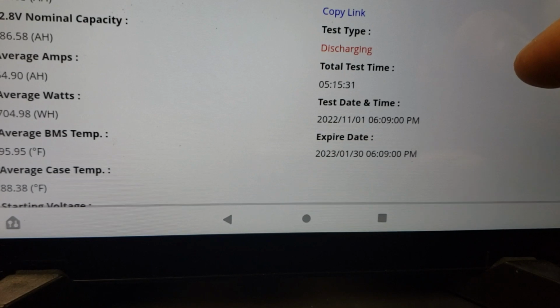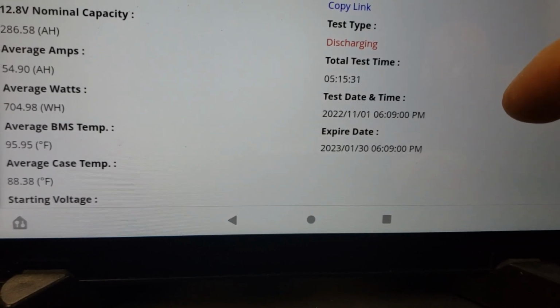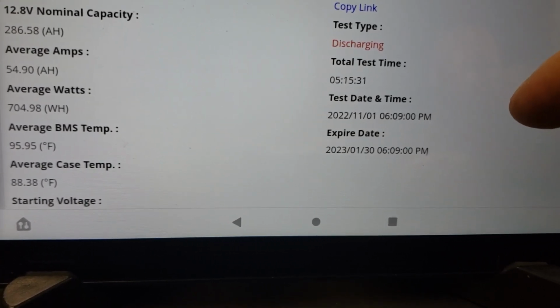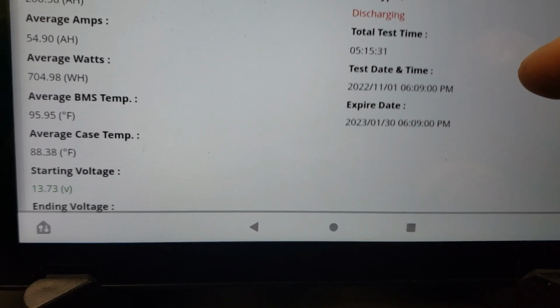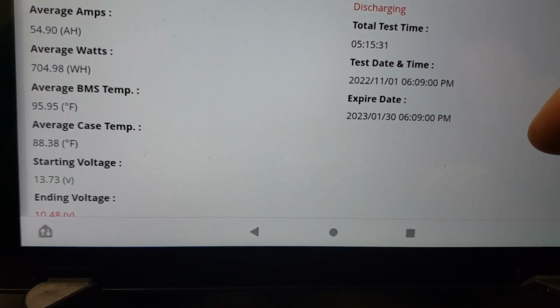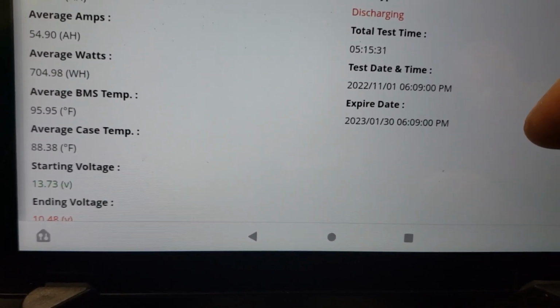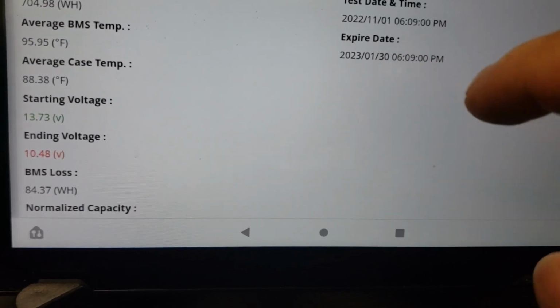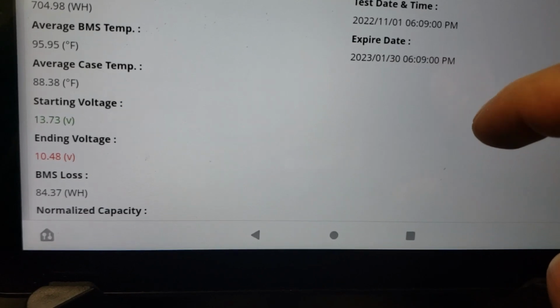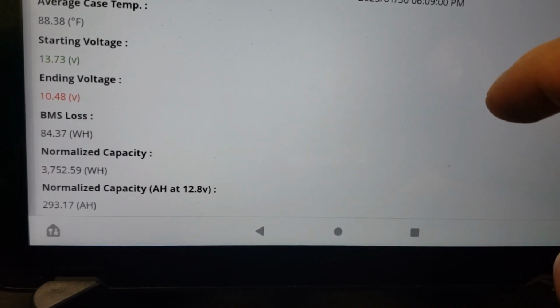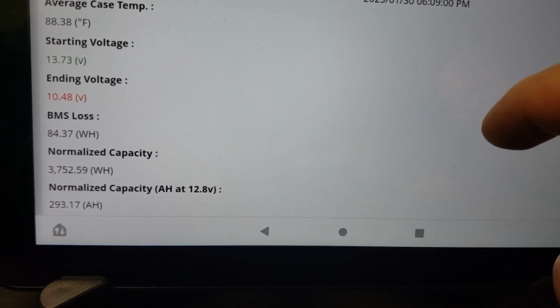We were testing at an average of 54.9 amps, and our average watts was 704.98, or 705. The average BMS temperature was around 96 degrees Fahrenheit, and about 88 degrees Fahrenheit for the case. Starting voltage was 13.73 and ending voltage was 10.48.